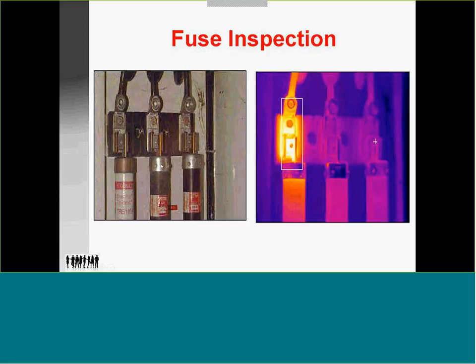You see here that is also a violation. You have 2 cartridge fuses, one of a dissimilar type from a different manufacturer. This is strictly prohibited. All fuses in a 3-phase must be of the same manufacturer. The clear time can be several cycles different. So these 2 might clear, and this one might be lagging a little bit so it stays energized and the arc is going.